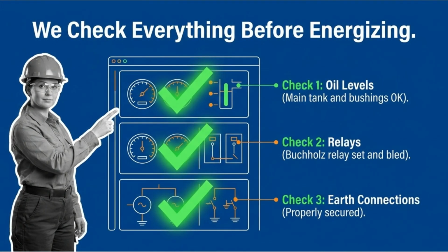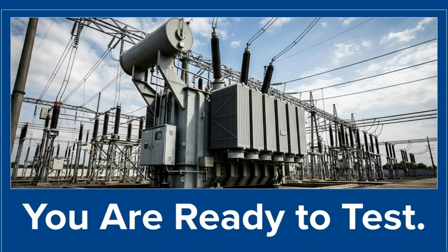Before energizing, perform a final check. Ensure oil levels are correct, confirm that relays like the Buchholz are properly set, and verify that all earth connections are secure. With these diagnostic procedures complete, your transformer is ready for service.